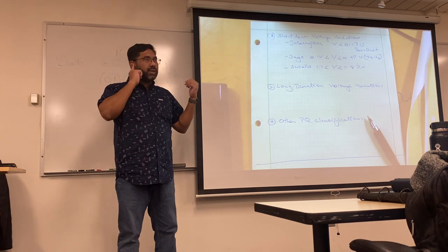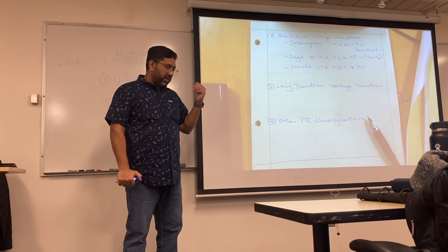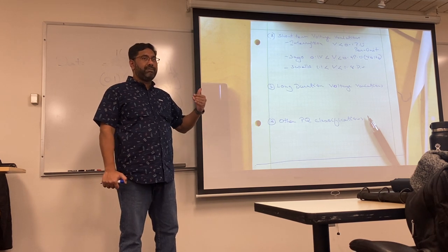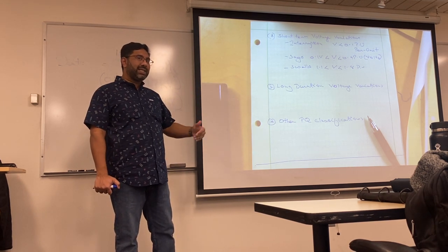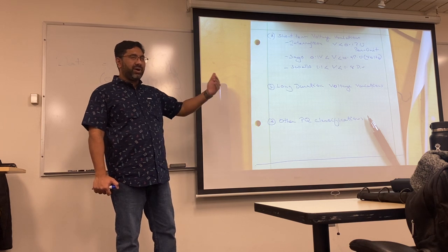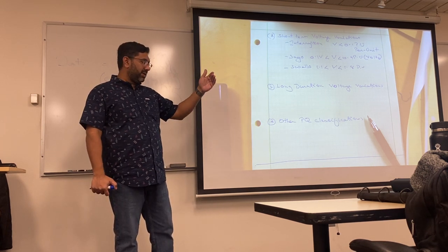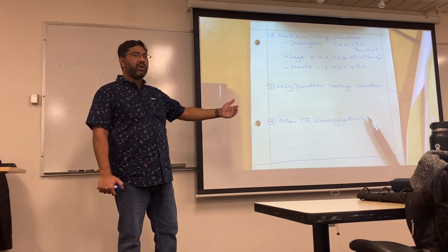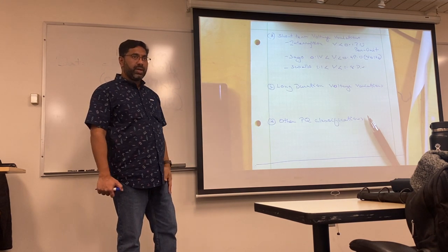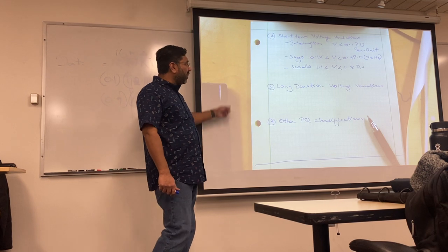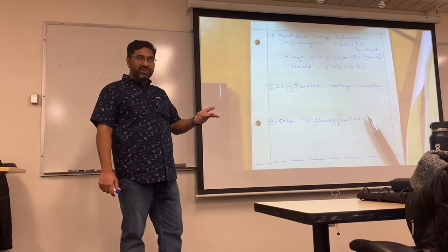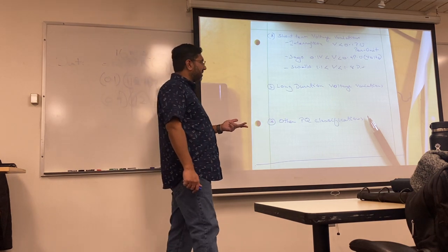I deal a lot with solar fields right now, and with all the solar folks, the point where we sort of do a handshake is at the substation. Sometimes even beyond that. But at the substation, if you give me these 4 things, I can assure you that the power quality is going to be so and so. And how we ensure that is we tell them what equipment to use, how to use it, and when to use it. Because otherwise you just can't control it.